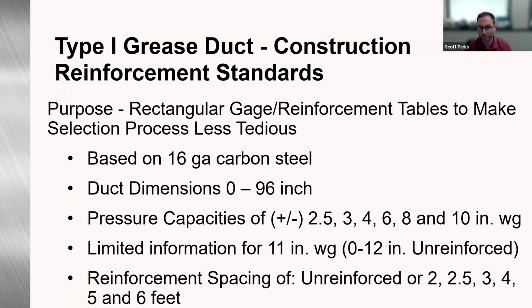The pressure capacities for positive and negative can be used on the makeup air side as well. But pressure capacities are 2.5, 3, 4, 6, 8, and 10-inch water gauge. Some very limited information for 11-inch water gauge, like literally up to 12 inches unreinforced. So that's it. And then it's going to be based on reinforcement spacings of either unreinforced, 2, 2.5, 3, 4, 5, or 6 foot reinforcement spacings.